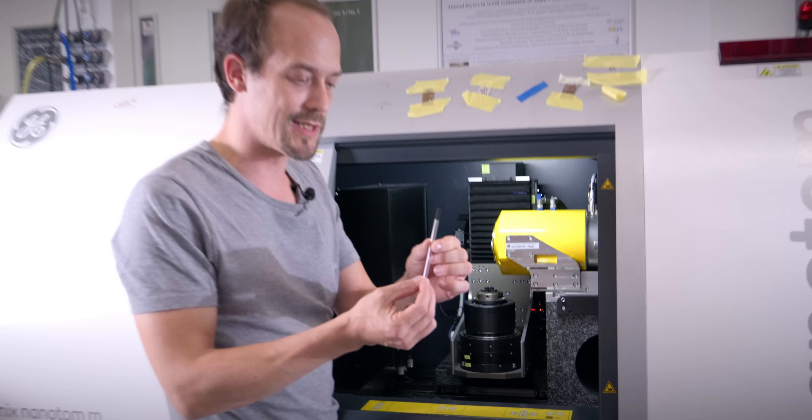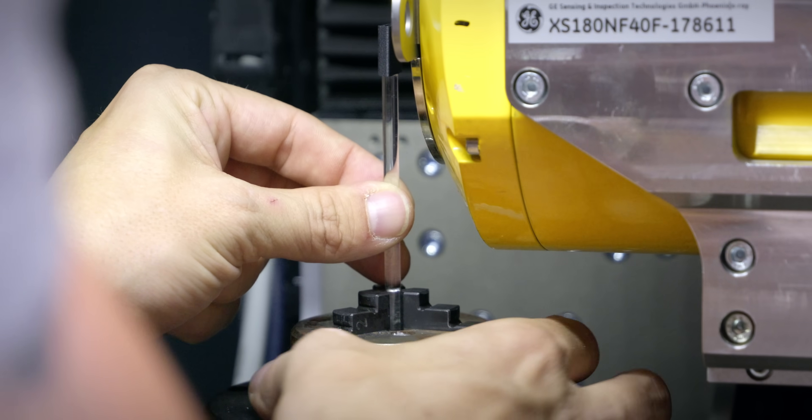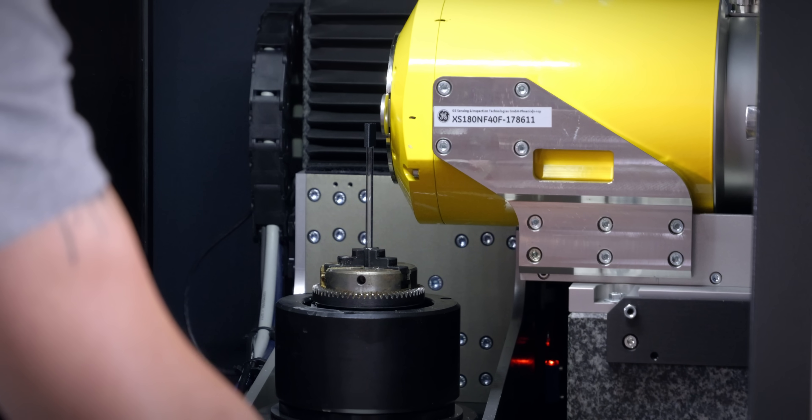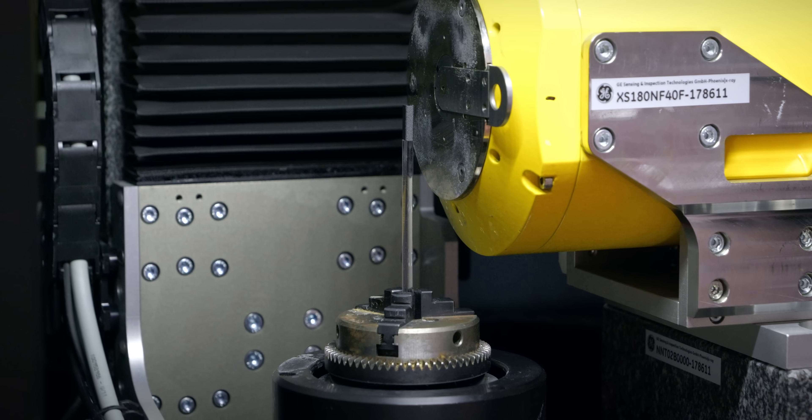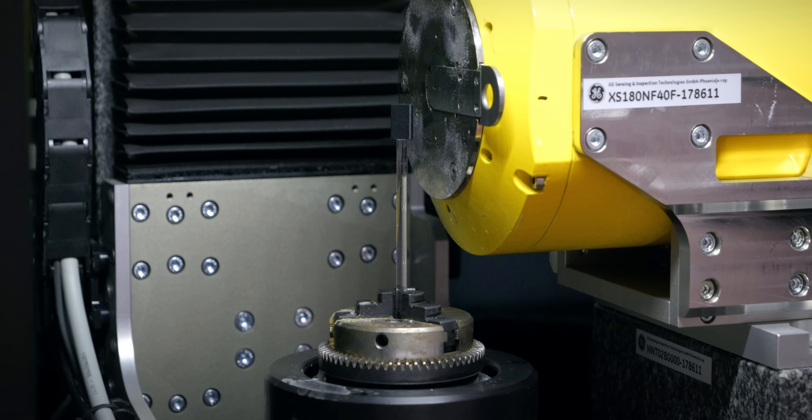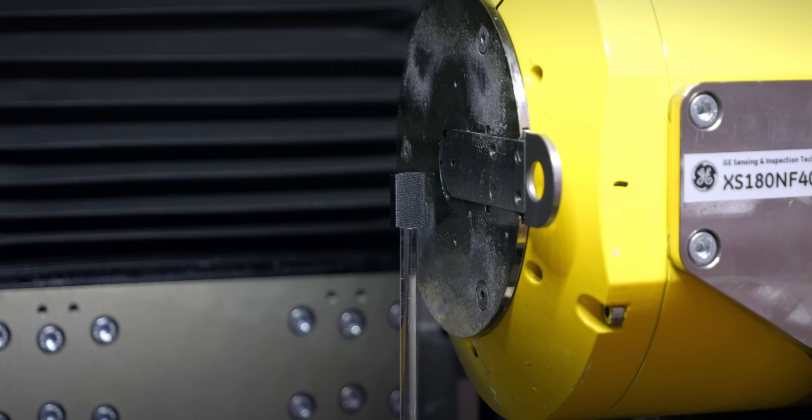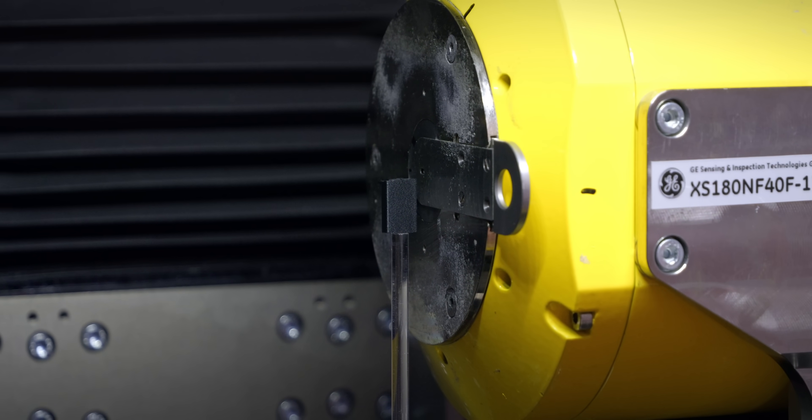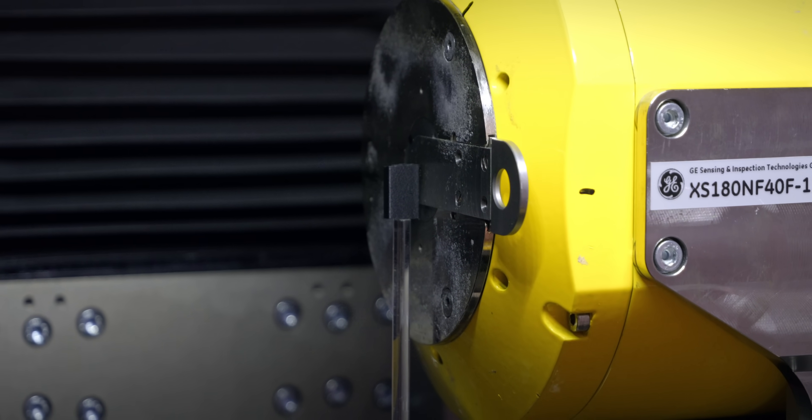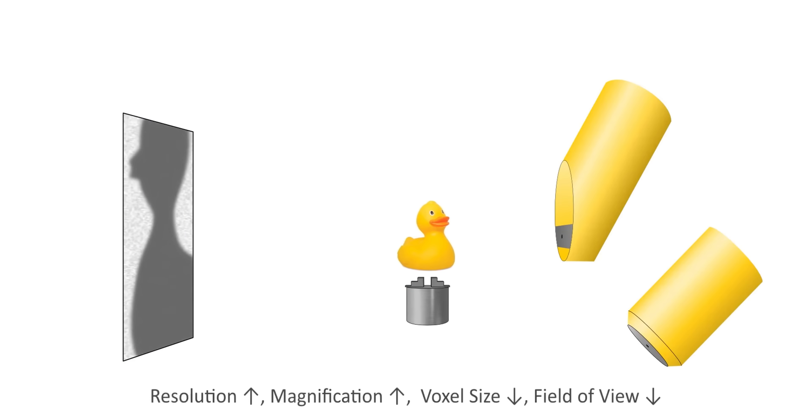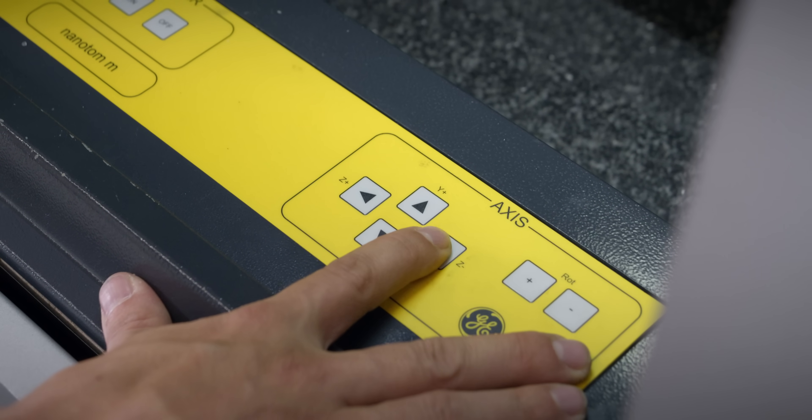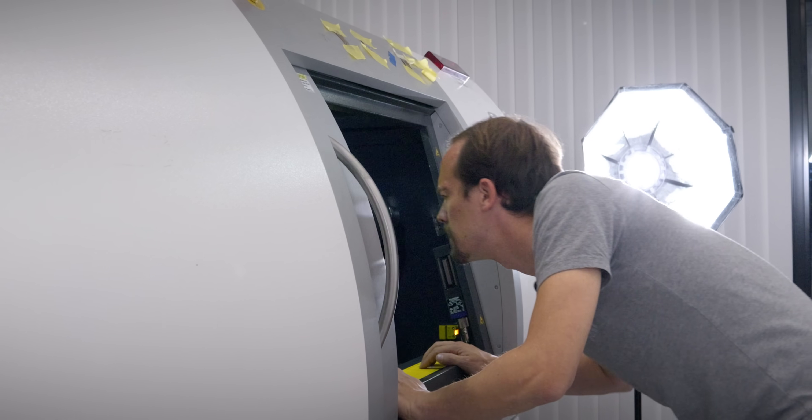This is our sample. I glued it to this little plastic tube just to get it in here. As you can see, I can now bring my sample super close to the source, and I can actually rotate my part. Because this is a conical x-ray, the closer I get with my part, the more I magnify whatever I'm looking at, because the x-rays start here in the middle and they basically shoot out. So I can magnify in two ways. I can get closer with my sample to my x-ray tube, or I can even push this screen farther away. I prefer to get as close as possible to get a good magnification because that's where I get the best resolution.